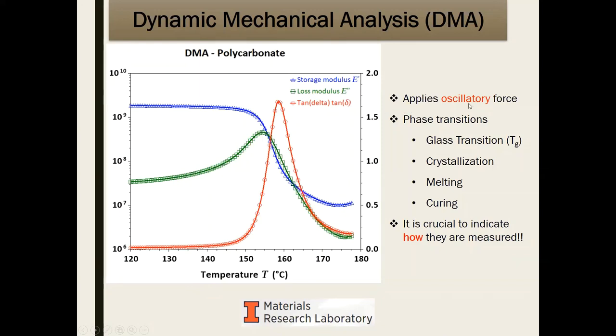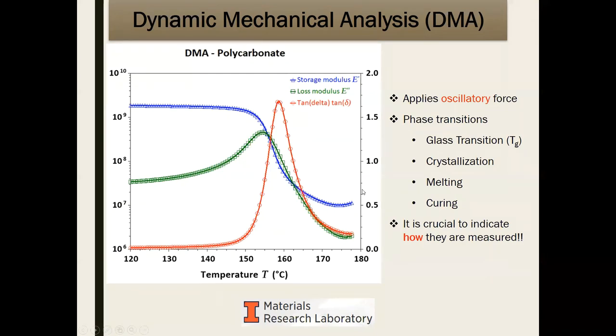Dynamic mechanical analysis involves applying an oscillatory force instead of a linear force, giving a completely different set of data: storage and loss moduli, and tan delta (loss divided by storage modulus). This tells you about phase transitions, crystallization, melting, and curing. When reporting dynamic mechanical analysis data, make sure to clearly state all experimental parameters — frequency, strain amplitude, geometry — because there are many more variables than in a simple stress-strain measurement, and this is critical for reproducibility.